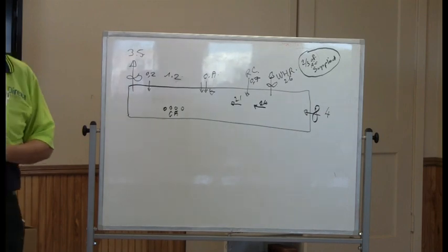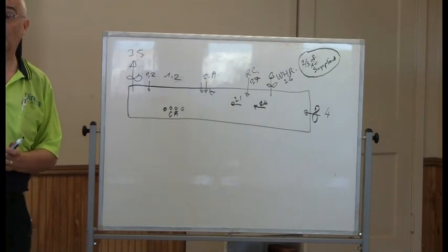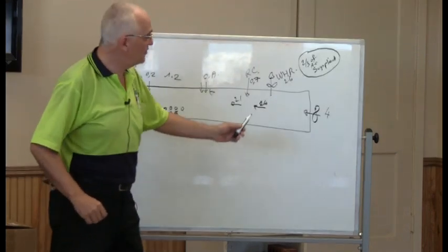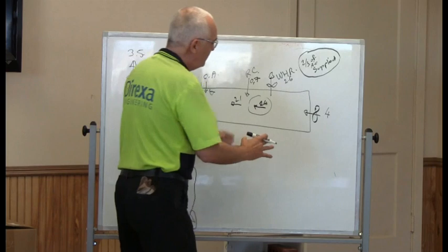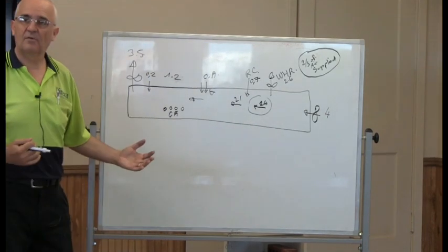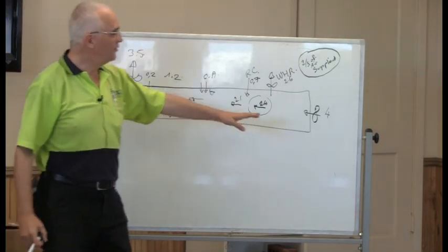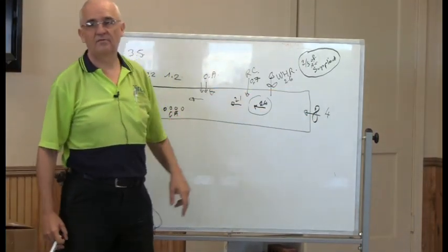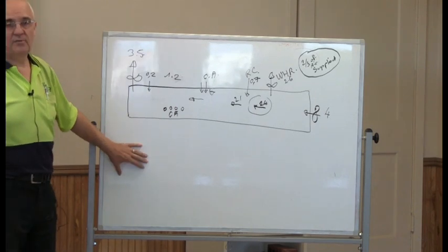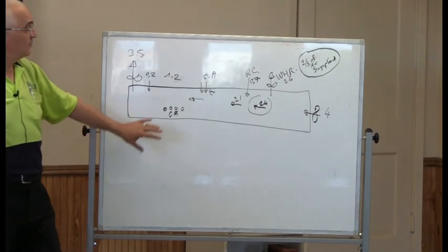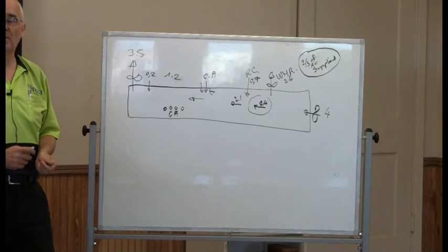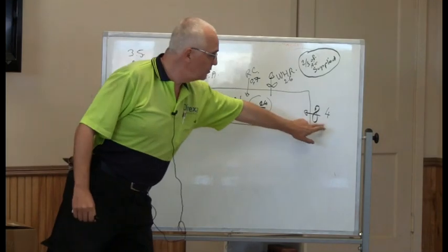But if you take a Lingle kiln or a Keller kiln or a JMAC kiln or whatever, they are not necessarily based on exactly the same values. But you still need enough air here to cool down the product. You still need enough air passing through the firing zone to distribute the heat, etc. Again, if you reduce this, you need to reduce that because you still need to have enough air passing through. And the critical thing when we speed up or slow down the push rate on the kiln is to maintain those specific ratios.